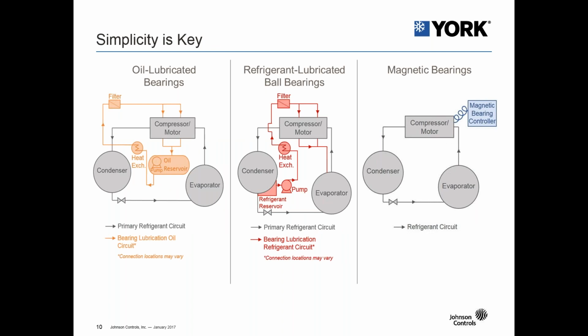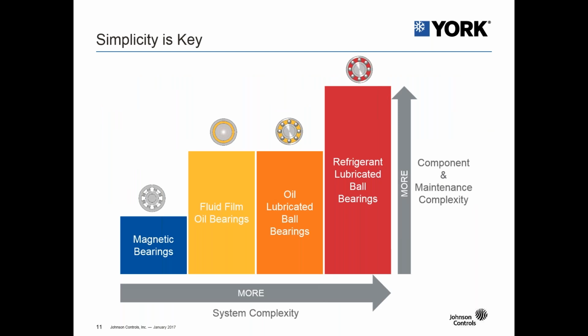So as we put all these systems side by side, simplicity is really the key. When you look at the oil lubricated bearings and the refrigerant lubricated ball bearings, there's really no difference between the system setup. So there's still a reservoir, the heat exchanger, the pump, and the filter, whereas the magnetic bearings do not have all of those additional connection points and components. So from a system complexity standpoint, the magnetic bearings have the least amount of complexity when you're looking at all the components and the maintenance of those systems.